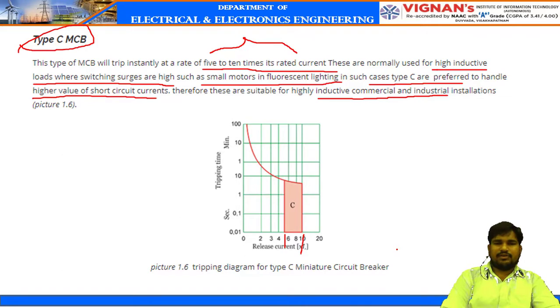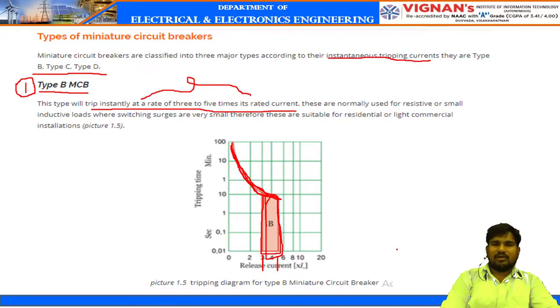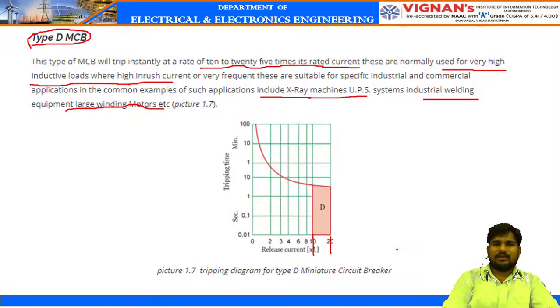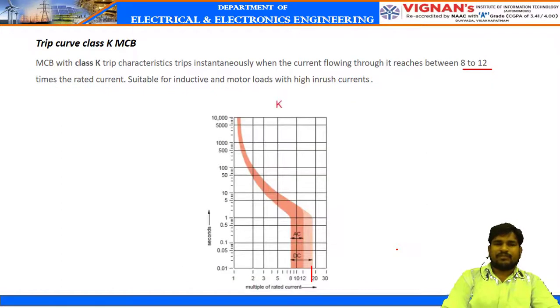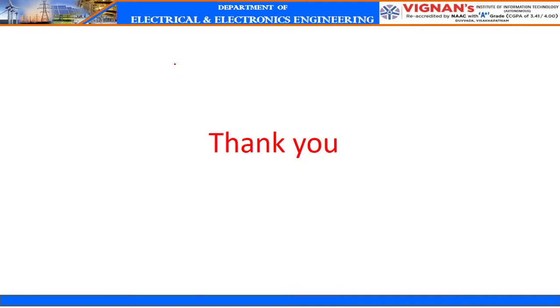For example, if you want to withstand up to 5 to 10 times of rated current, we use type C MCB, or if you want to withstand up to 3 to 5 times of rated current, we use type B MCB. If it is more, that means 10 to 25 times of rated current, we use type D MCB for AC. For DC, we use either type K or type Z according to the characteristics.